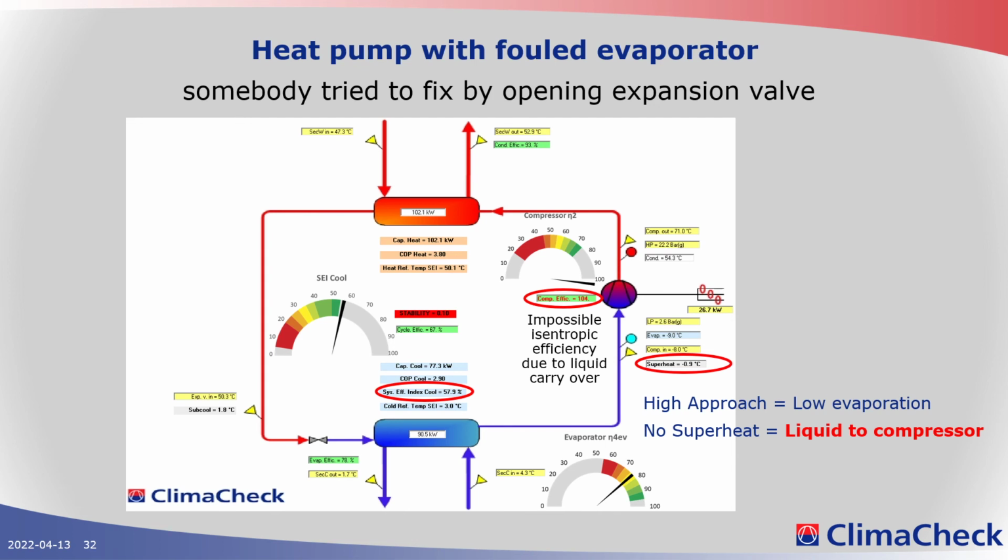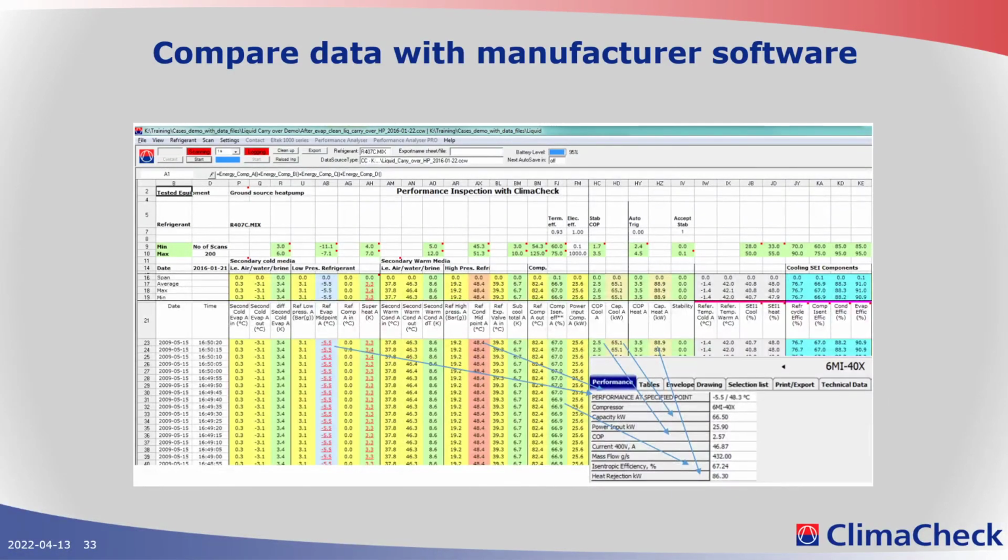So when you know the performance of your heat exchangers, it's easy to address the problem. Here is just another comparison where the data points are taken from the measurement, entered into Copeland's compressor software, showing that the system is behaving extremely close to the measured data.